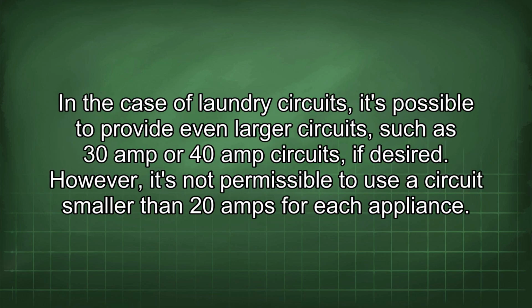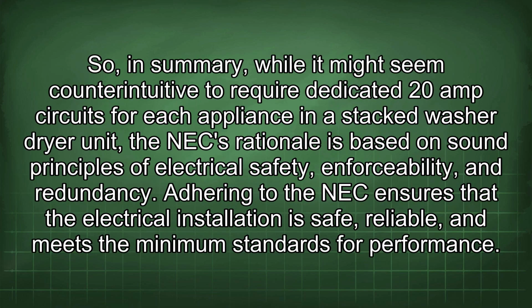In the case of laundry circuits, it's possible to provide even larger circuits, such as 30-amp or 40-amp circuits, if desired. However, it's not permissible to use a circuit smaller than 20 amps for each appliance. So, in summary, while it might seem counterintuitive to require dedicated 20-amp circuits for each appliance in a stacked washer-dryer unit, the NEC rationale is based on sound principles of electrical safety, enforceability, and redundancy. Adhering to the NEC ensures that the electrical installation is safe, reliable, and meets the minimum standards for performance.